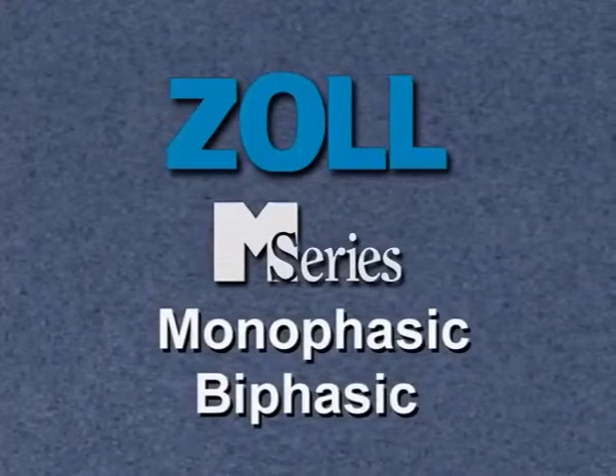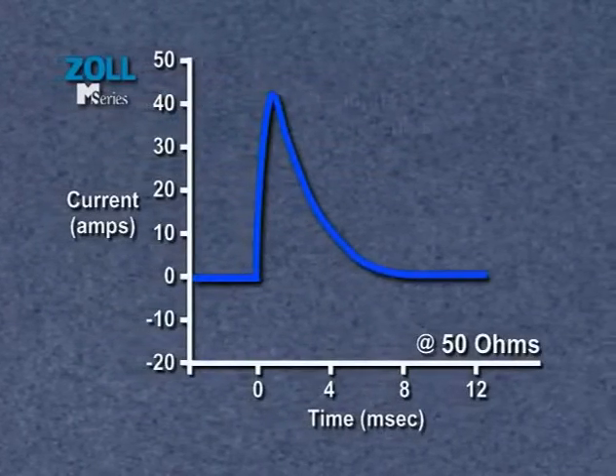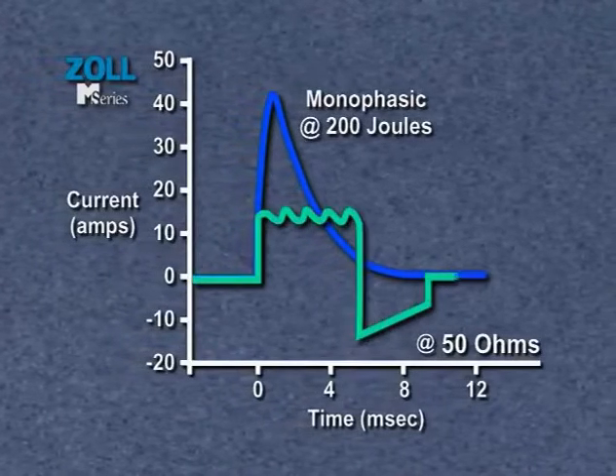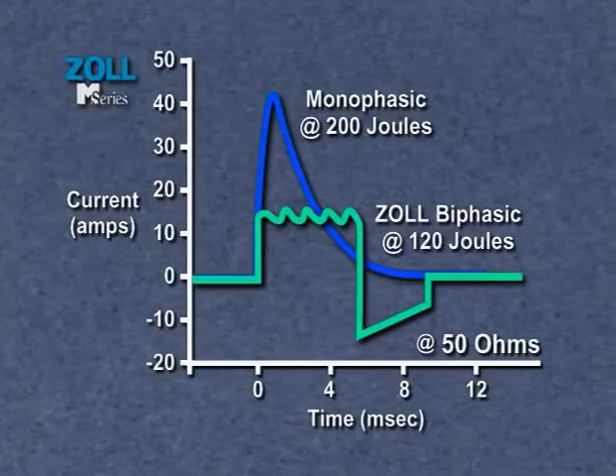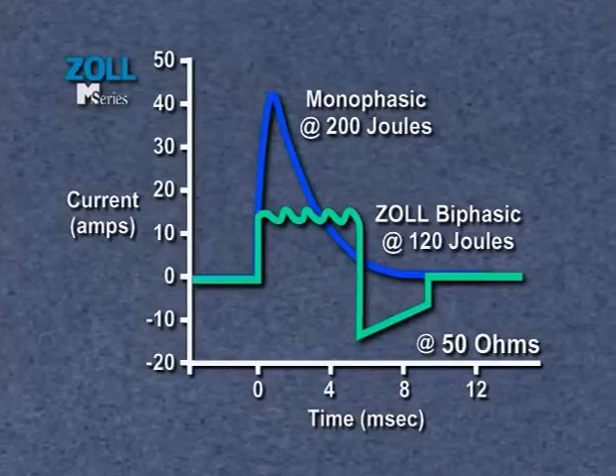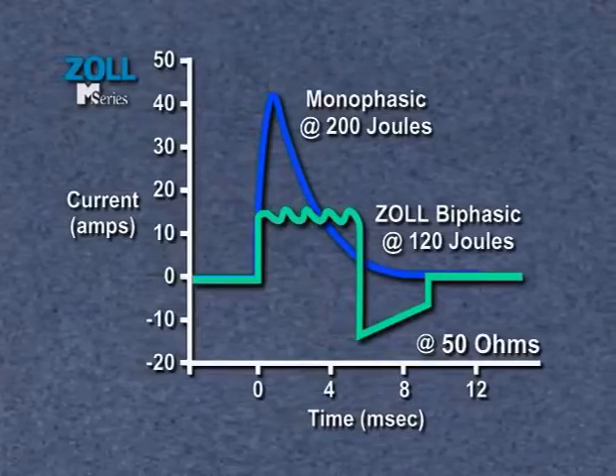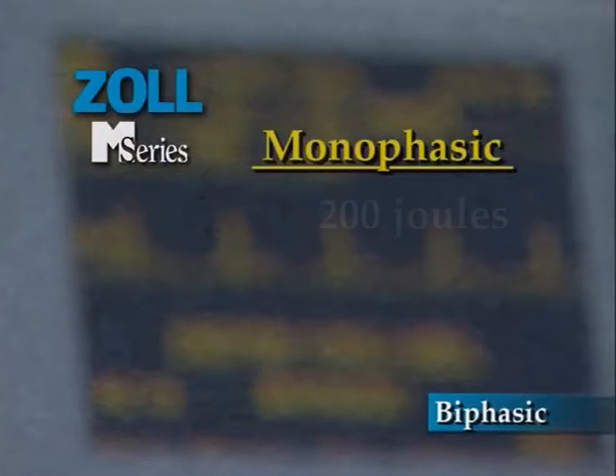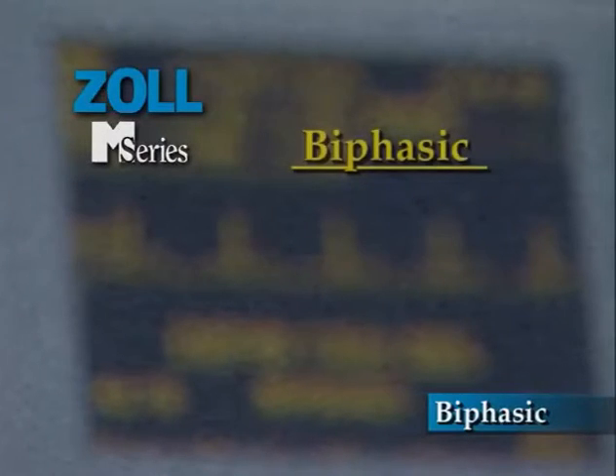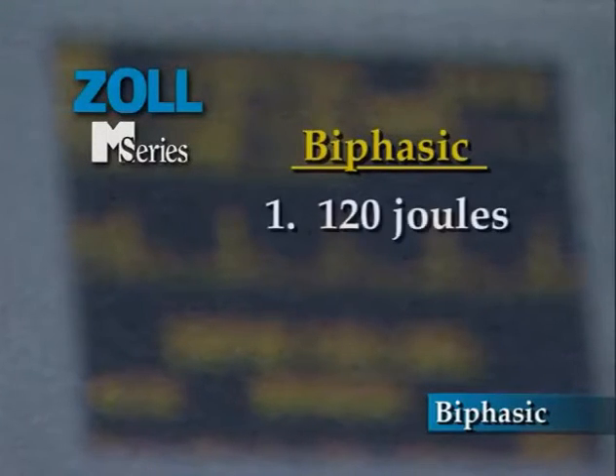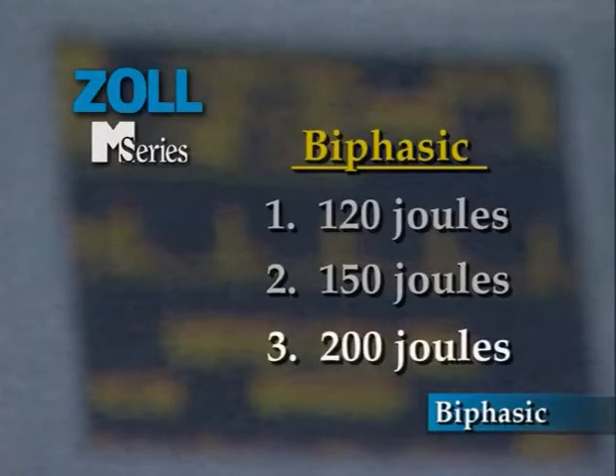M Series are now available with a choice of 2 defibrillation waveforms. Some M Series are equipped with a monophasic waveform, and some offer ZOLL's new low-energy rectilinear biphasic waveform. The rectilinear biphasic waveform offers superior defibrillation capabilities at lower energy settings. The suggested 3-shock VF protocol for monophasic waveforms is 200, 300, and 360 joules. The suggested biphasic 3-shock VF protocol is 120, 150, and 200 joules. Successive low-energy shocks should remain at 200 joules.